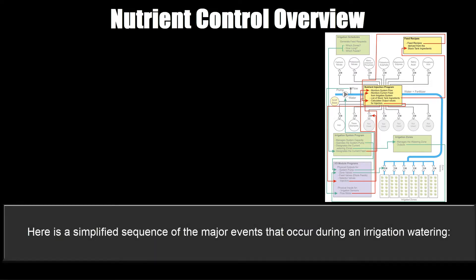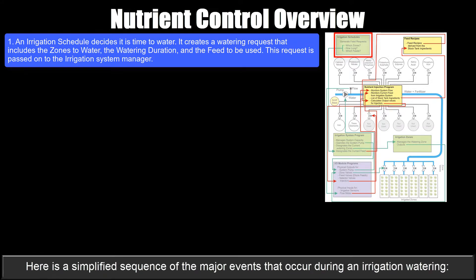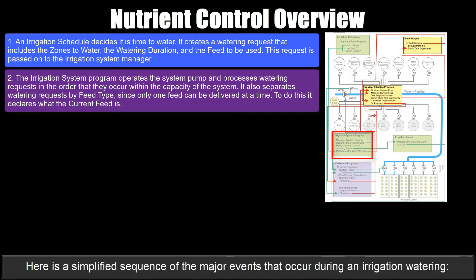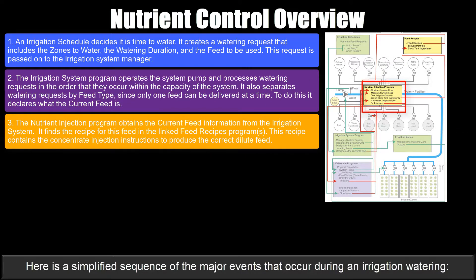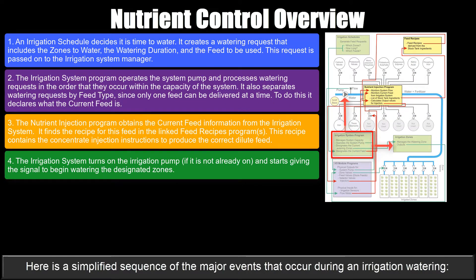Here's a simplified sequence of major events during an irrigation watering. An irrigation schedule decides it's time to water and creates a watering request that includes the zones to water, the watering duration, and the feed to be used. This request is passed to the irrigation system manager. The irrigation system program operates the system pump and processes watering requests in the order they occur within system capacity. It separates watering requests by feed type since only one feed can be delivered at a time, and declares what the current feed is. The nutrient injection program obtains the current feed information, finds the recipe in the linked feed recipes program, and that recipe contains the concentrate injection instructions to produce the correct dilute feed. The irrigation system then turns on the pump and signals to begin watering designated zones.